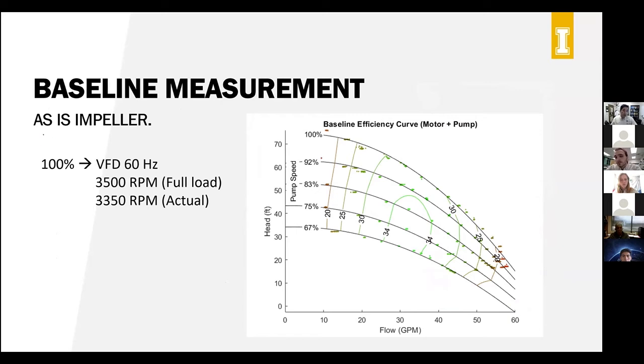So from the data we collected, we calculated the efficiency from how much power it is taking, the pressure difference between inlet and outlet, and the flow, and plotted it in this chart. Each point here is color coded. The greener the point, the more efficient that point is. You can see that the points are greener in the middle and redder on the outer peripheries. So these are less efficient and those are more efficient. We also have these iso-efficiency lines to show the contour of equal efficiency. And the most we got is about 35% efficient.